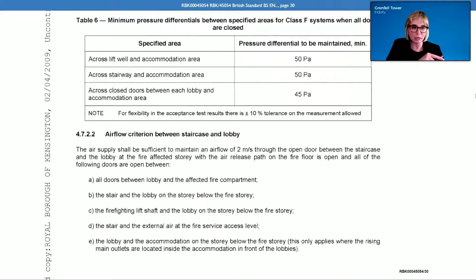Yeah. Now, in summary, would you agree that this testing is done because you need to be sure that the system is powerful enough to maintain pressure if different scenarios occur during the fire event? Totally agree with you, yeah, you're right. So opening different doors will simulate what might happen in real life, where other occupants escape, or where you enter the firefighting phase, yes? Yeah, totally agree. And can we agree that during the firefighting phase, you may have a situation whereby the fire brigade have set up on the lobby below and have trailed their hose through the stair door below, up the stairs, through the stair door, and then through the flat door. So you'd have 3 doors open at that point. Yeah, absolutely.